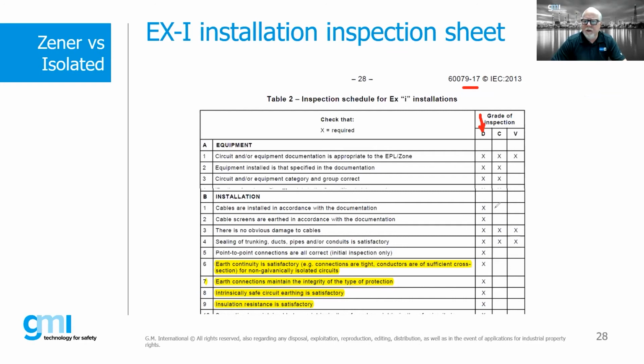Are the cables installed in accordance with the documentation? Yes, yes, yes, yes. And oh, by the way, I have to make sure my earth continuity is satisfactory for non-galvanically isolated circuits, right? I need to check that out. So if I'm doing Zener diodes, that's absolutely what I need to be looking at. Notice that we also have to check our earth connections, maintain the integrity of the type of protection. Is the intrinsically safe circuit earthing satisfactory? Insulation resistance is satisfactory. These are all things that are requirements before we put this equipment into service. So sometimes people use intrinsically safe and they're building it as part of their packages, right? But this has to be done before this equipment is actually put into service. So it's important to understand this. It could be done at the OEM level or it could be done at the end user level, but at some point in time, it needs to be done.